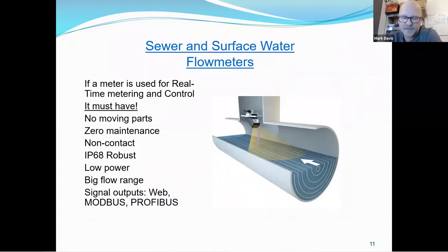Sewer and surface flow meters. The main challenge here is, of course, you have a part full pipe or a channel. But if you're going to use a meter for real-time control, we'll start to look at some of the requirements. It must have no moving parts. You can't have anything in the flow. It will get cruddy, and we'll have a look at some pictures in a minute. It has to be robust. IP68 means it can be submerged without being destroyed.